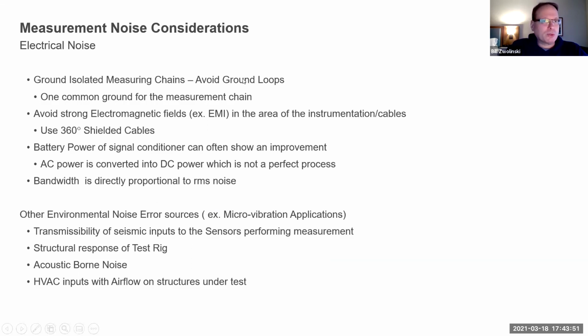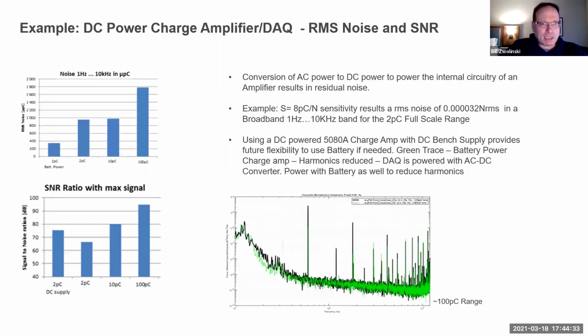Anyway, there are a lot of sources of noise, and some of them are related to electrical, ground loops, or electromagnetics perhaps, or battery, or AC power to DC power conversion. And obviously wider bandwidths are directly proportional to RMS noise. So all these things factor into the electrical noise. When doing microvibration, there are always issues to do with seismic noise inputs, structural response of the test rig, and acoustic borne noise. If you've got high level acoustics, you can actually excite the measurement structure, the actual table, and maybe even the test article itself. So a lot of detail there.